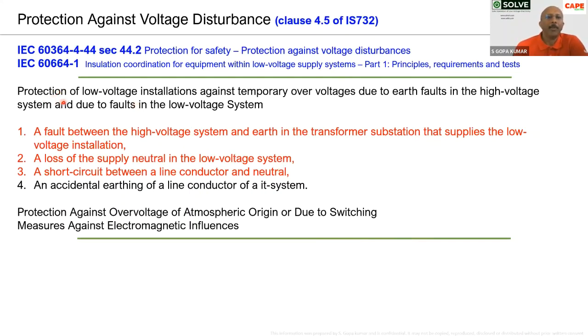So today's subject is the protection of low voltage installation against temporary overvoltage. You know very well that our voltage is 230/400 volt. Normally, sometimes we also say 240 line to neutral and 415 phase to phase or line to line. In the presentation, the voltages which I am referring to are applicable to 230 volt line to neutral and 400 volt line to line.